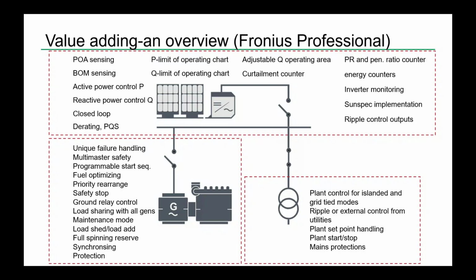You have multi-master functionality, priority handlings, synchronizing protection. In addition to this, you have the full J1939 implementation to the engine ECU. So there's a lot of power management functions that you get. But for the utility incomer side, you have the plant control for all the islanded modes and the grid-tied modes, and in this case it is the plant control where we can actually react when something happens.